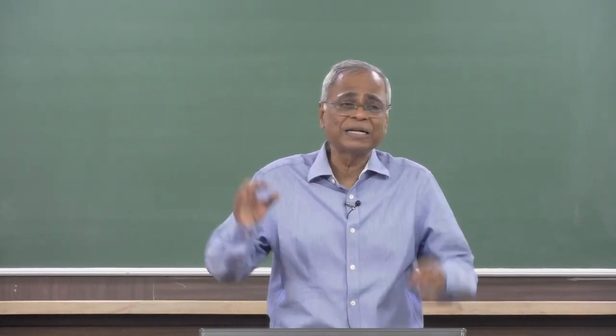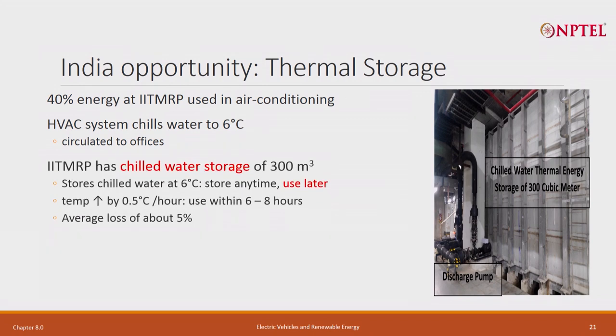Essentially it is acting like a storage — whenever there is excess electricity I store energy in the form of chilled water, and whenever there is a deficit I use that chilled water to cool the building without running the chiller. All that is needed is a thermal storage tank. Will the temperature keep going up slightly? If kept at 6 degrees centigrade, depending on thermal insulation it may go up by 0.5 degree per hour — so in 6 hours it goes up by 3 degrees. With more thermal storage it could be only 0.25 degree per hour. We will assume average loss is about 5 percent.